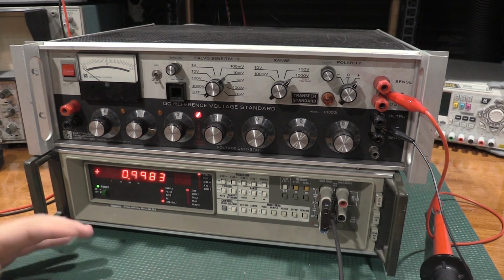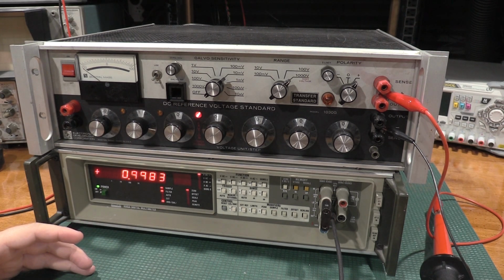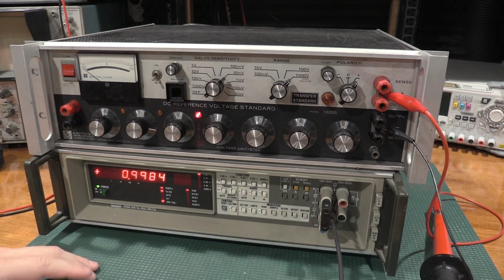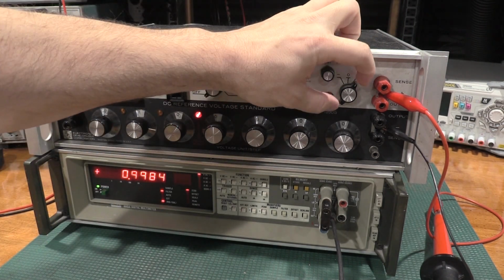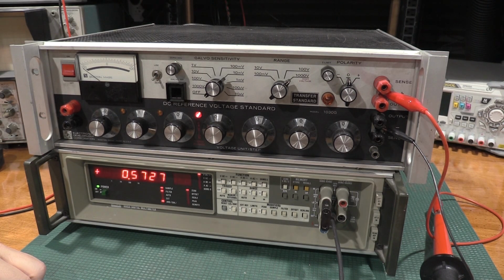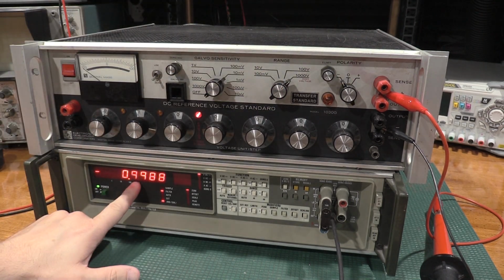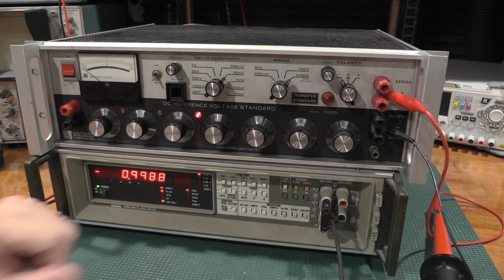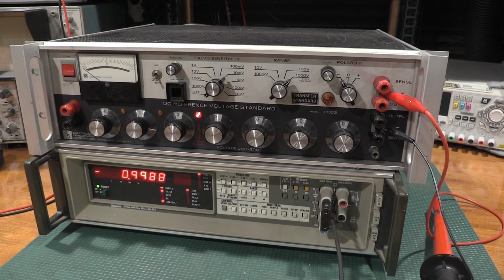So that's how all the high voltage probes work. It's just a matter of what the division is and what their voltage ratings are. I definitely don't want to touch anything over here right now because it's 900 volts. And we can even prove that by reversing the polarity, which is a neat trick this EDC can do. So now we have a negative 998 volts. So they work positive and negative. Both polarities are fine. It's just a matter of making sure the ground connection is hooked up first. Not hooking up the ground connection first, you don't get the division effect and can damage equipment, damage people.